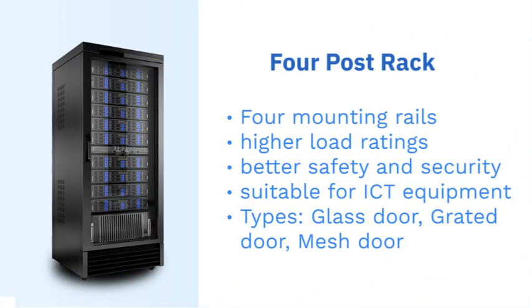Second type is four post racks. Four post racks are mostly suitable for ICT equipment. They provide better safety and security. They have a front door, back door and side doors. They are used for higher load ratings. In a data center you will find mostly four post racks. They have different types, like glass door, grated door or mesh door.